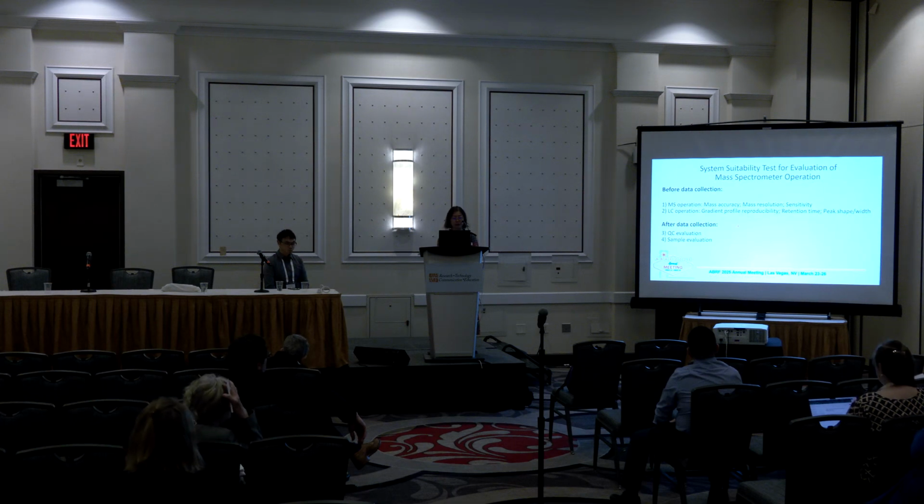Before the data collections, we'll evaluate the mass operation by mass accuracy, mass resolution, sensitivity. We'll also evaluate LC operation by gradient profile reproducibility and internal standard retention time, internal standard peak shape, and width. After we finish data collections, we'll evaluate the QC, and we'll also evaluate our samples.